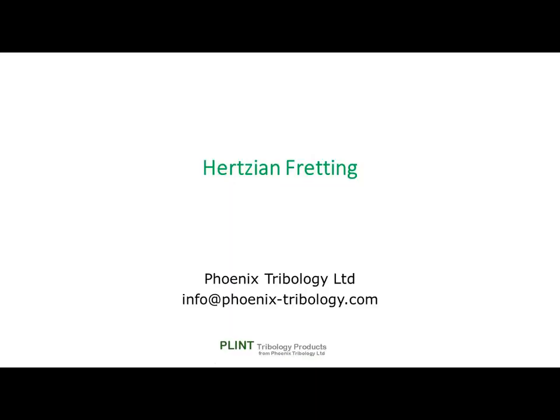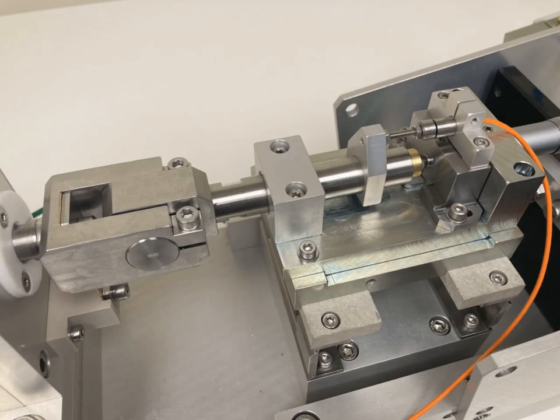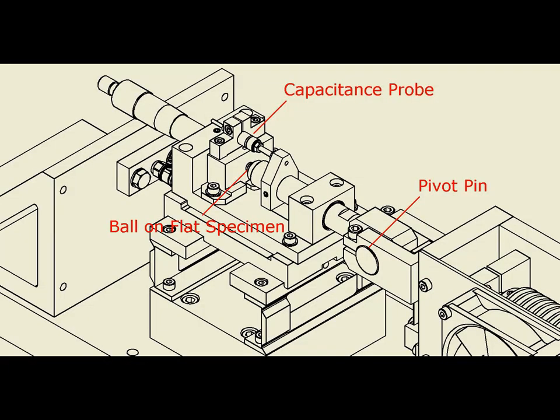The normal motion setup is used for Hertzian fretting, impact fretting, and depth sensing micro-hardness tests. For Hertzian fretting, a ball is loaded normally against a flat surface. The flexural bearing is replaced with a solid pivot pin. A micrometer is used to adjust the relative position between the ball and the flat specimen.